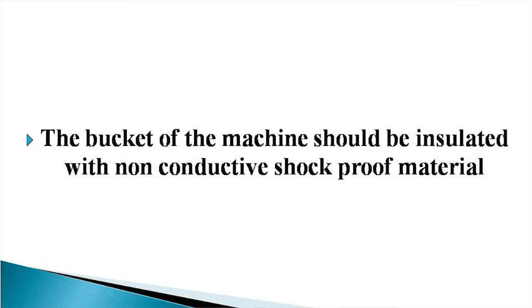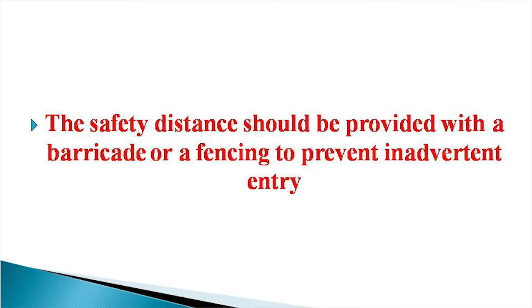Then the bucket of the machine which you are going to use near the overhead conductor, it is advisable to insulate it with a non-conductive, shock-proof material, so that in case of accidental contact with the conductor, the operator will not get an electric shock. Then the safety distance should be provided with a barricade or fencing to prevent inadvertent entry.